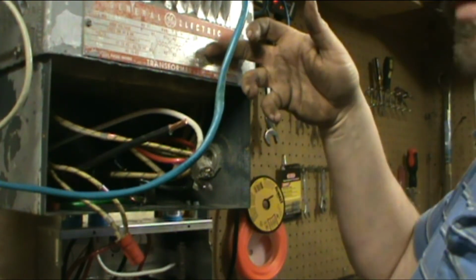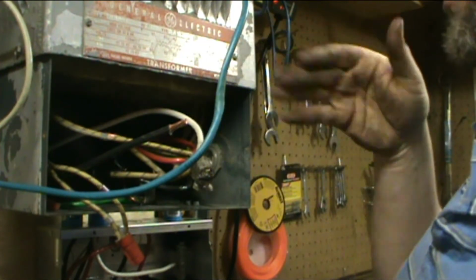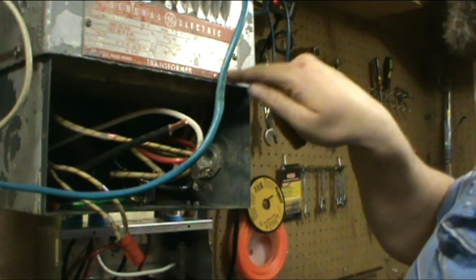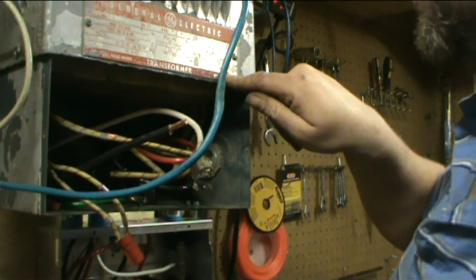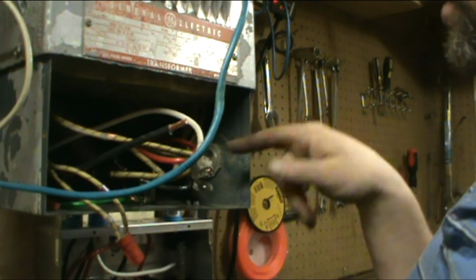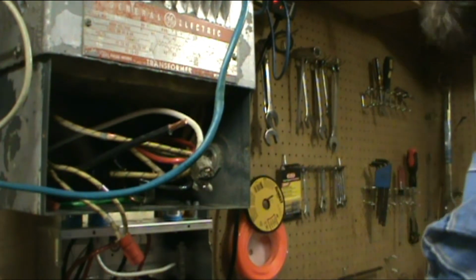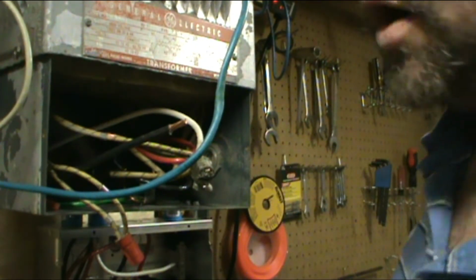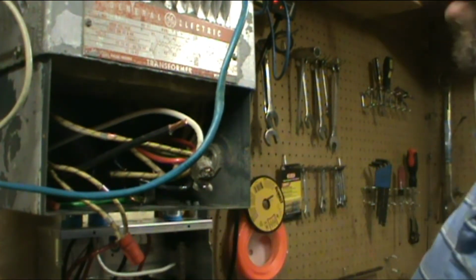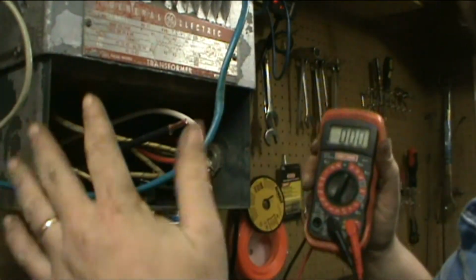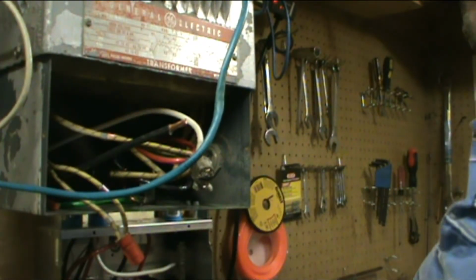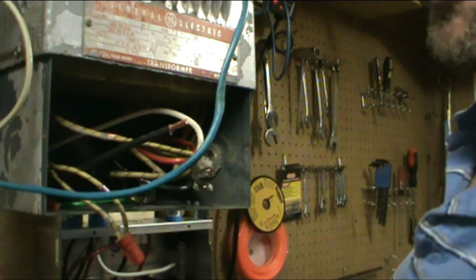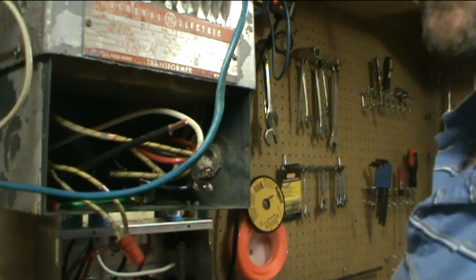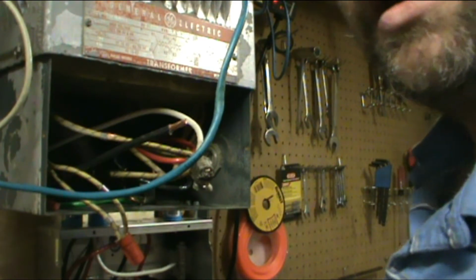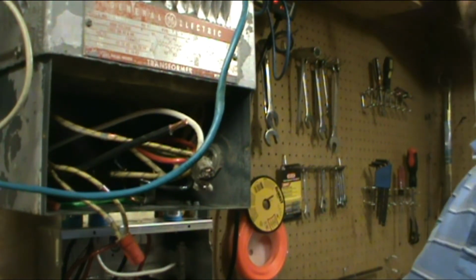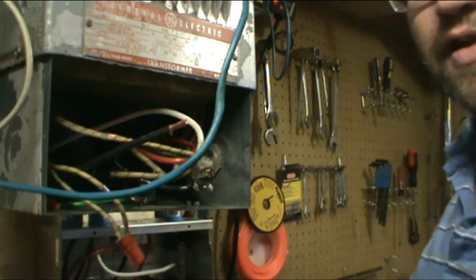So 240 in with split phase, which is it's wired up as split phase. My neutral is my center tap, which is X2, X3. Then that goes into my neutral. 240 and 240 either side, and that's how that's wired up. My other transformer, it's the exact same thing that's happening here, but in reverse. I'll be using the transformer there the way it's supposed to be. Primary is my 240, 480 in, and my secondary, which would be my 240, 120 output. So we'll get this all wired up, and I'll get back to you guys.